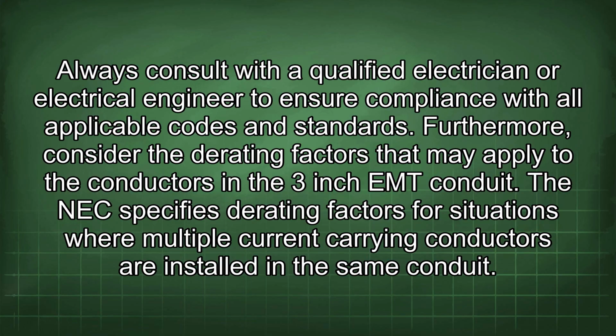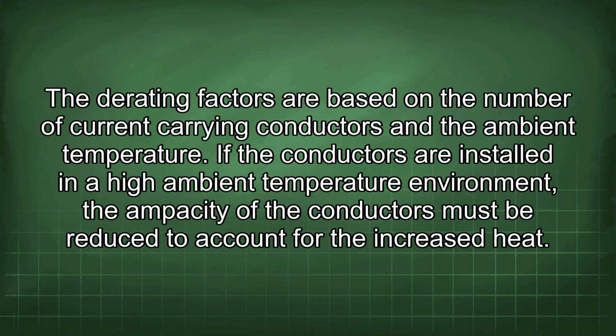The NEC specifies derating factors for situations where multiple current-carrying conductors are installed in the same conduit. The derating factors are based on the number of current-carrying conductors and the ambient temperature. If the conductors are installed in a high ambient temperature environment, the ampacity of the conductors must be reduced to account for the increased heat.